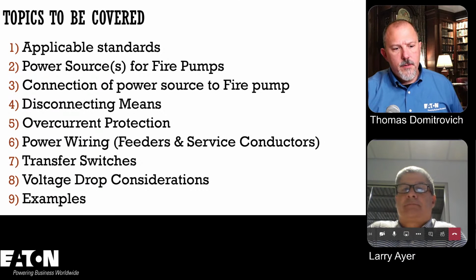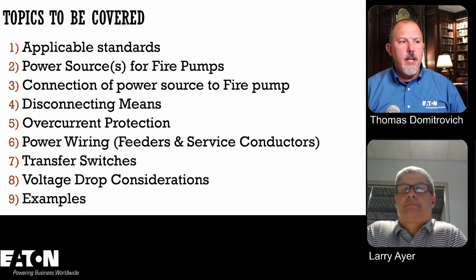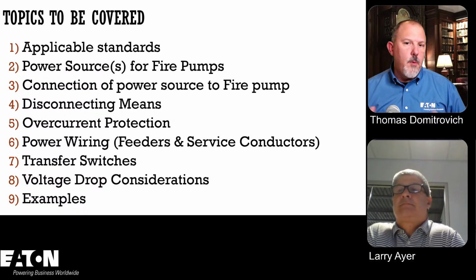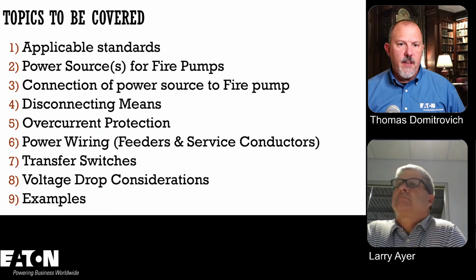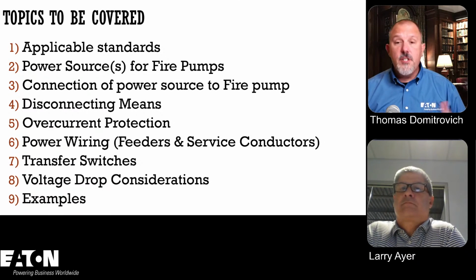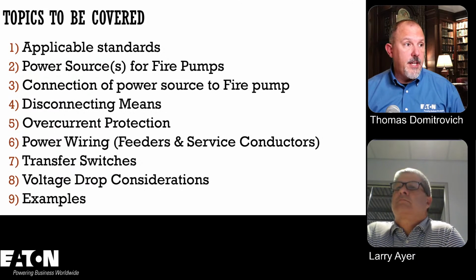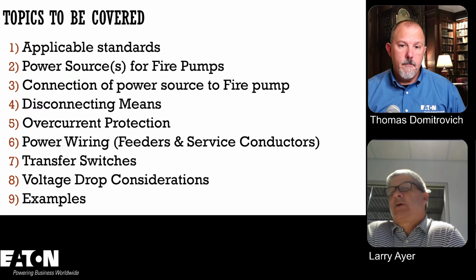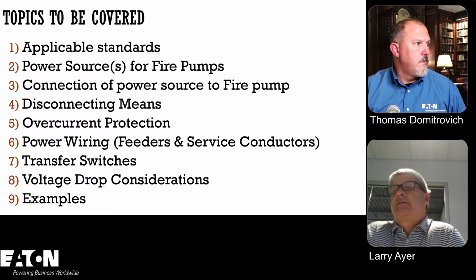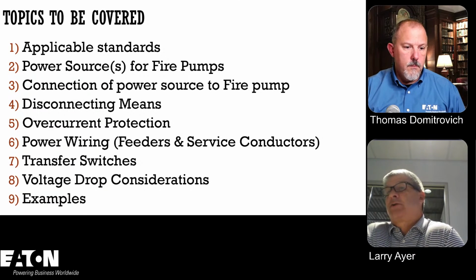Yeah, and then Chris says no concerns about a burst pipe. So I think he's thinking, could this be a wet location if you have a burst pipe? And I don't think we plan for a burst pipe or things of that nature, because if you lose the integrity of that, that's a whole other problem on your hands. We don't design things for a failure of a water pipe in your fire pump system. And a lot of times these fire pumps sit in these fire pump rooms for 15, 20 years without really being operational. So you want to make sure that you have it in a decent environment. You try to keep any foreign dirt and debris out of there, so that over time, when it's called upon, it's ready to go.